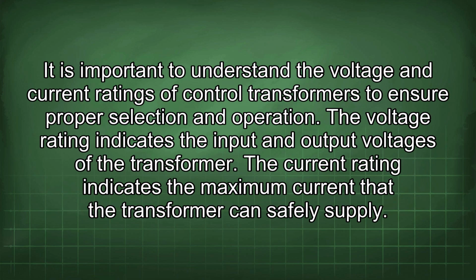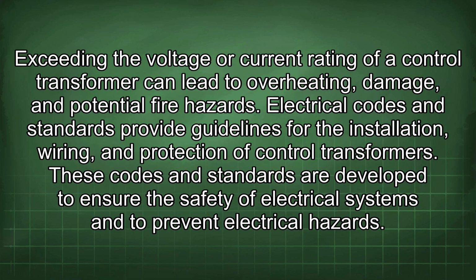It is important to understand the voltage and current ratings of control transformers to ensure proper selection and operation. The voltage rating indicates the input and output voltages of the transformer. The current rating indicates the maximum current that the transformer can safely supply. Exceeding the voltage or current rating of a control transformer can lead to overheating, damage, and potential fire hazards.